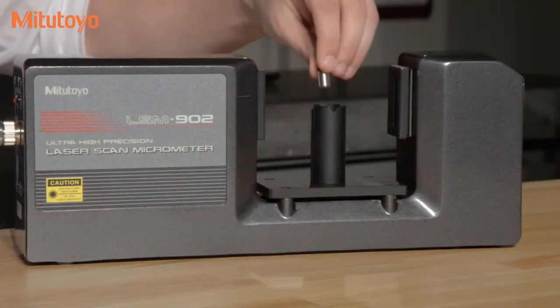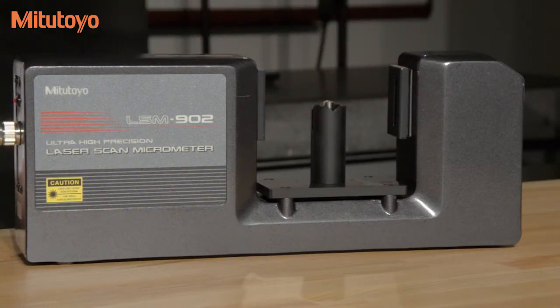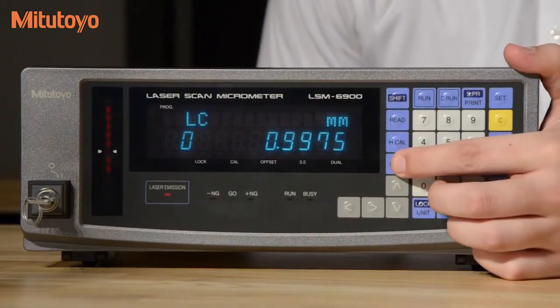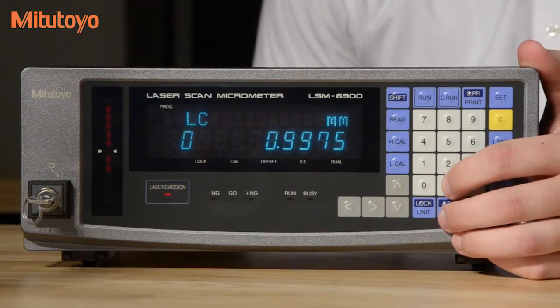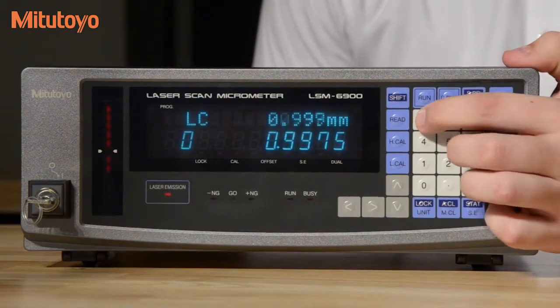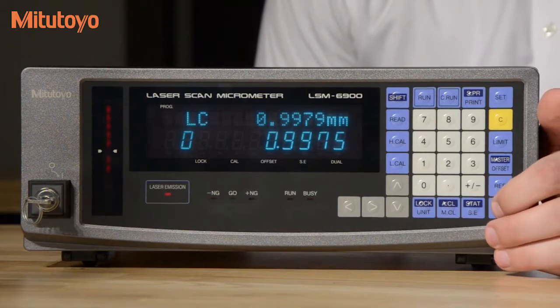First we're going to insert our smaller pin gauge. We're going to select our L.CAL button and enter the value of our lower gauge pin. This is 0.9979. We'll select enter when complete.